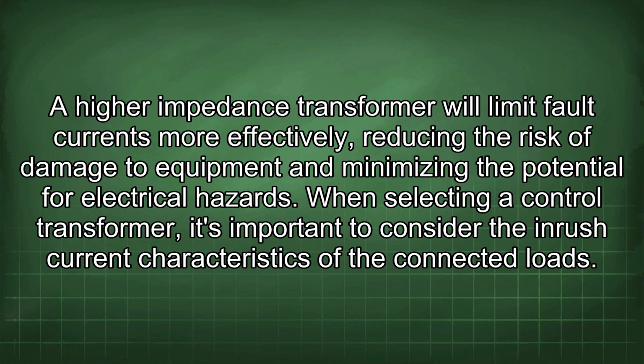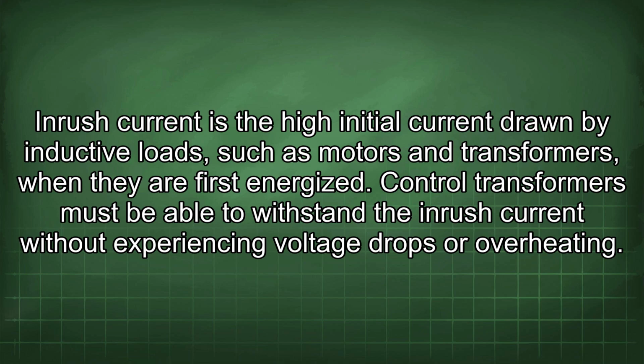When selecting a control transformer, it's important to consider the inrush current characteristics of the connected loads. Inrush current is the high initial current drawn by inductive loads such as motors and transformers when they are first energized. Control transformers must be able to withstand the inrush current without experiencing voltage drops or overheating.